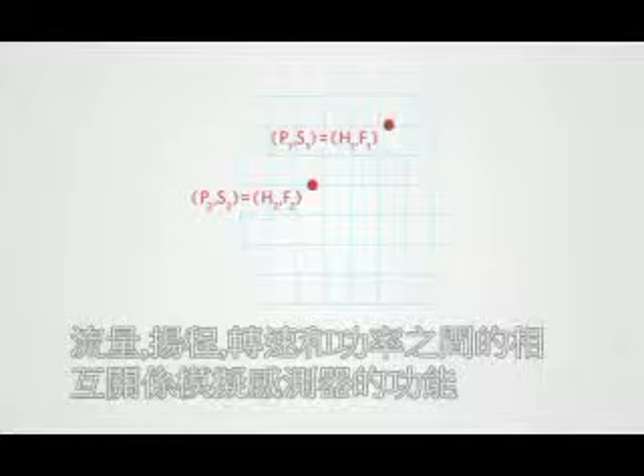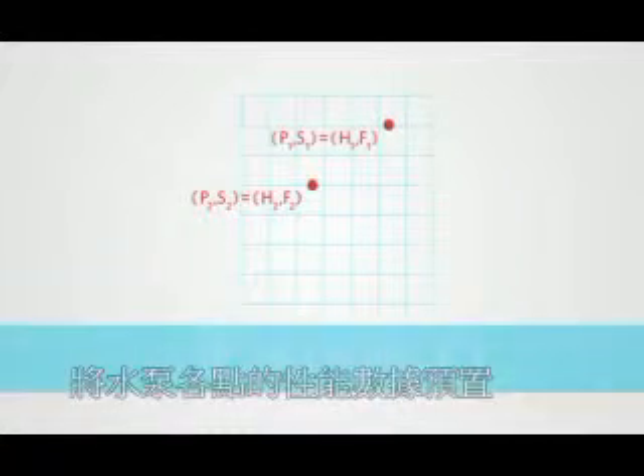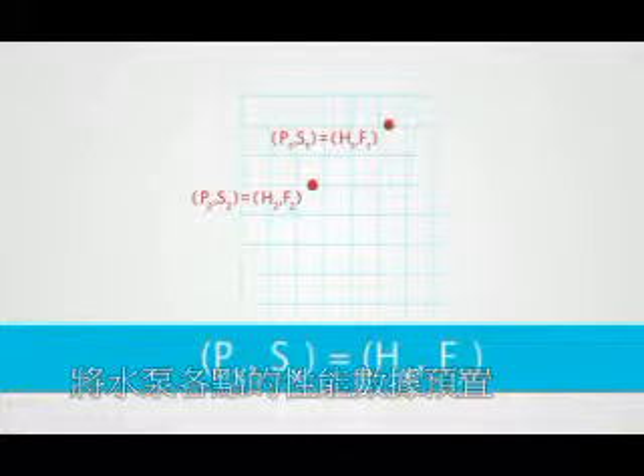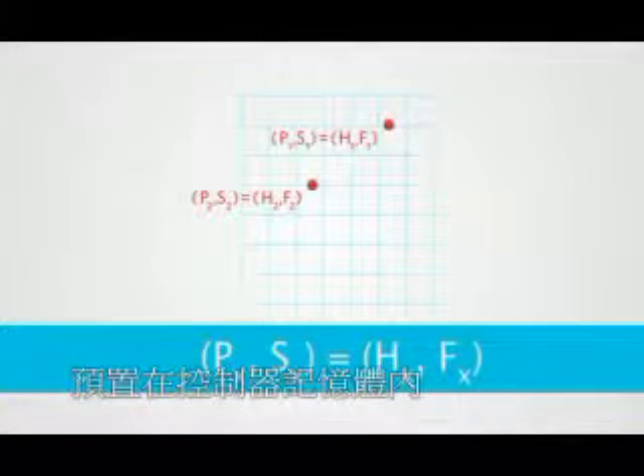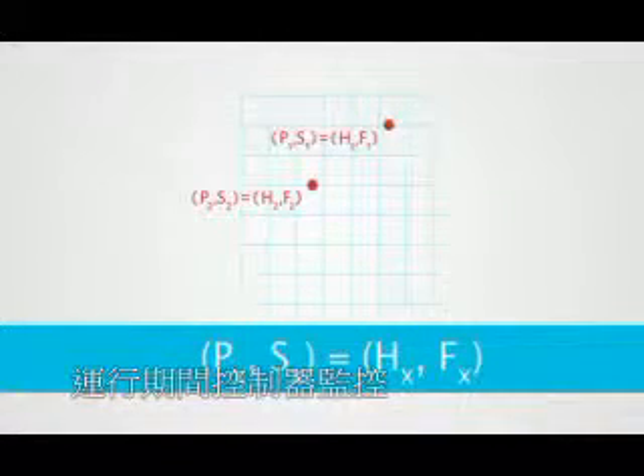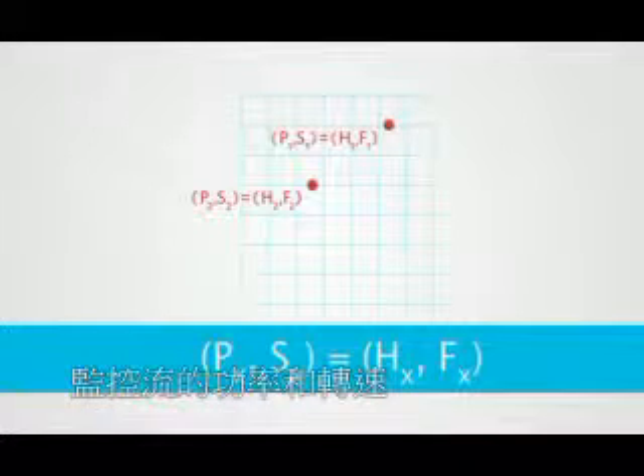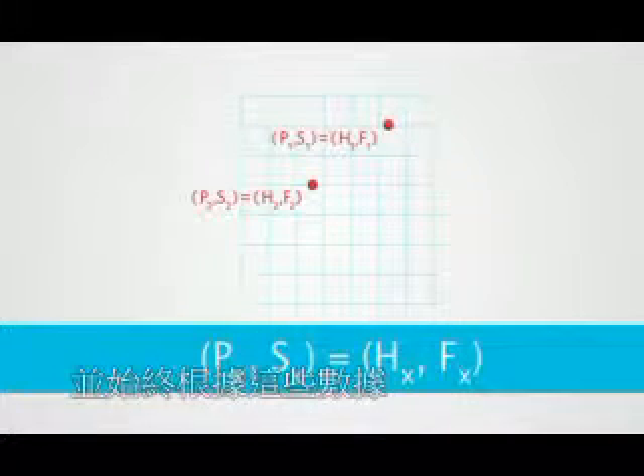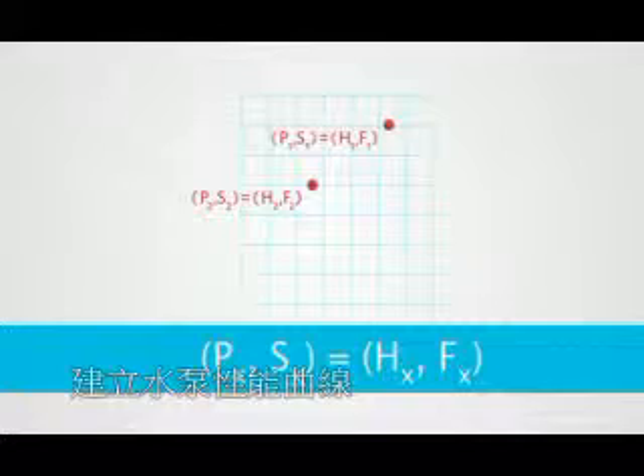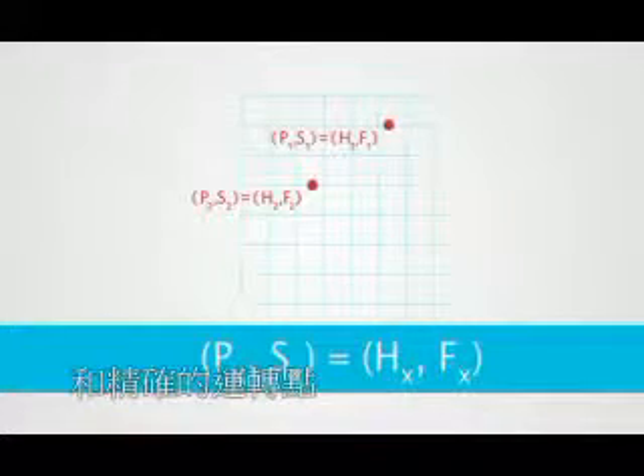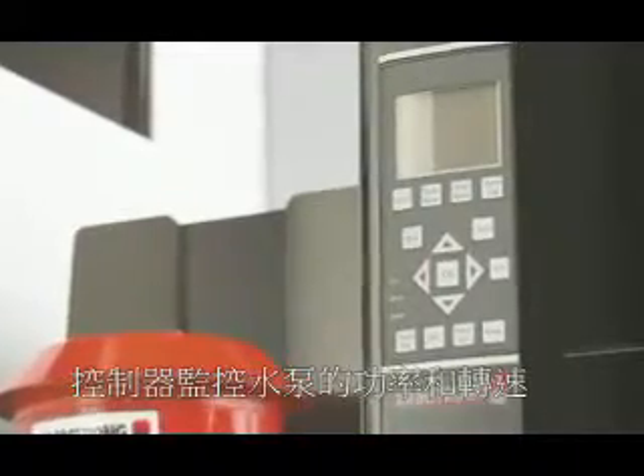Sensorless control mimics the performance of a sensor by using a pump's relationship between its flow, head, speed, and power. The controller's memory is programmed with the pump performance characteristic data map. During operation, the controller monitors the power and the speed of the pump and uses this data to establish the hydraulic performance and precise operating point of the pump at all times. The controller monitors the power and speed of the pump.